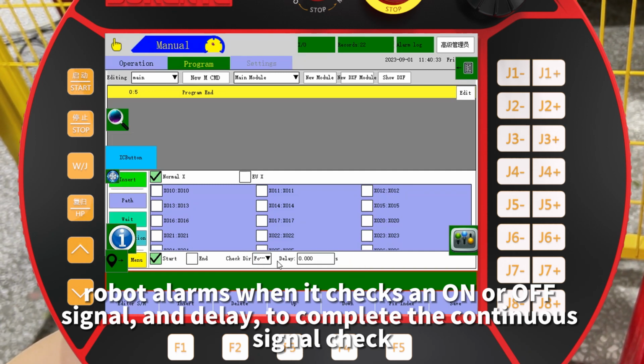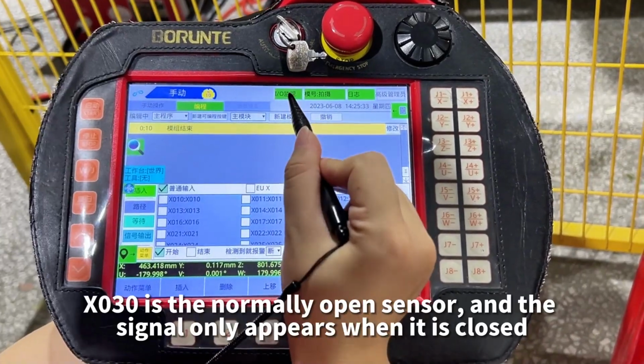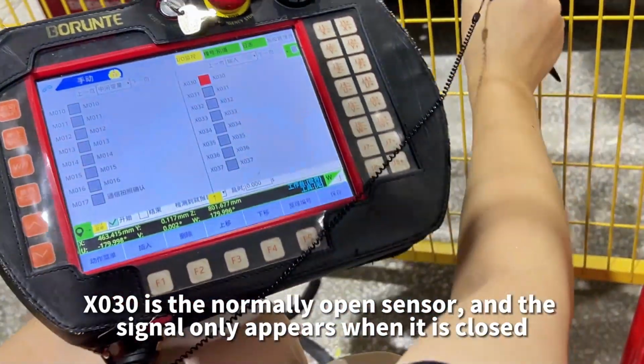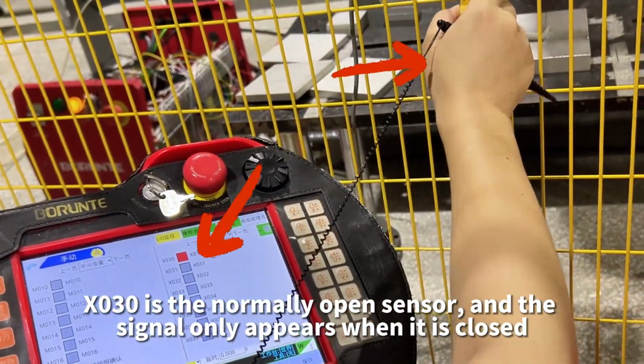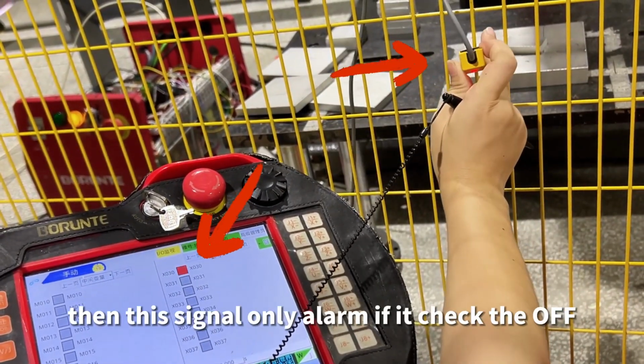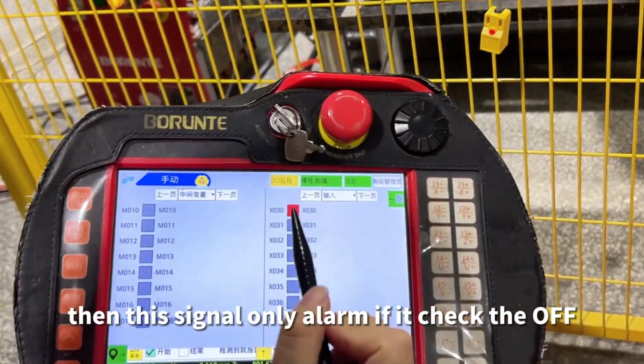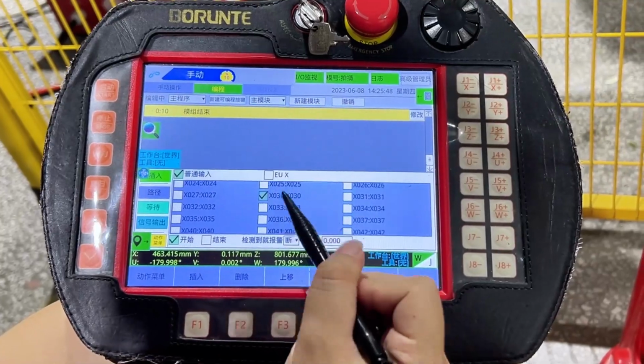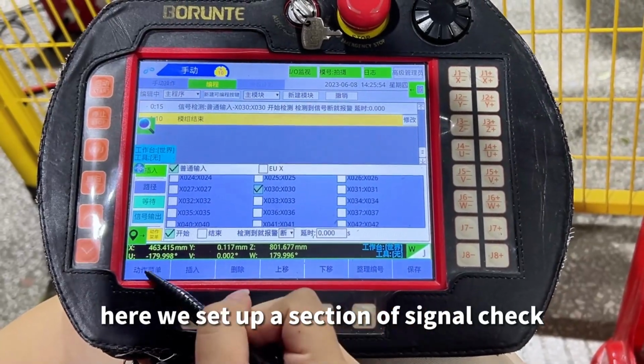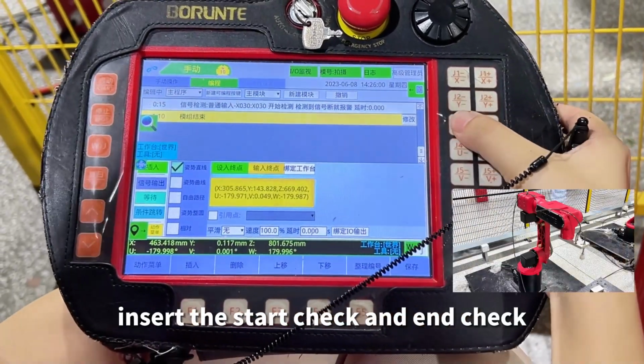To complete the continuous signal check, for example, X030 is a normally open sensor and the signal only appears when it is closed. Then this signal will only alarm if it is checked as off. Here we set up a section of signal check, inserting the start check and end check.